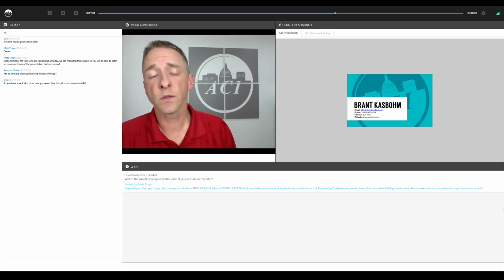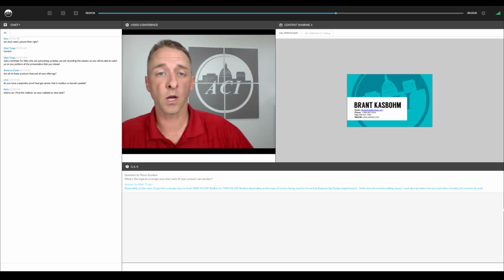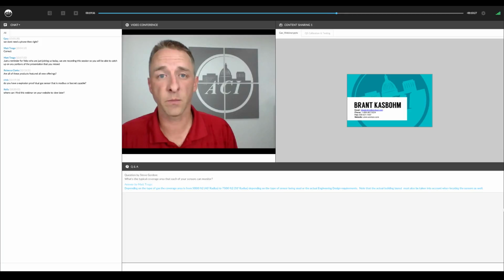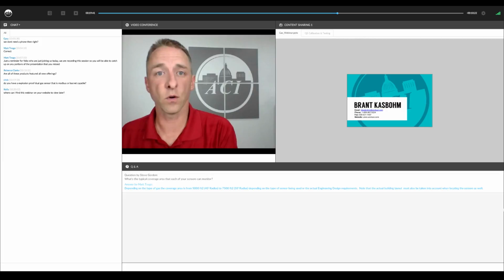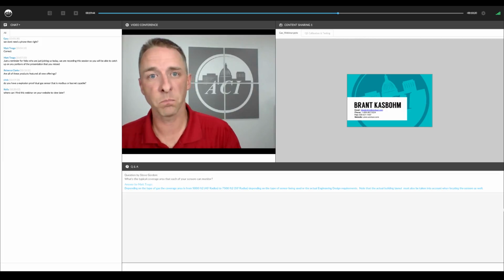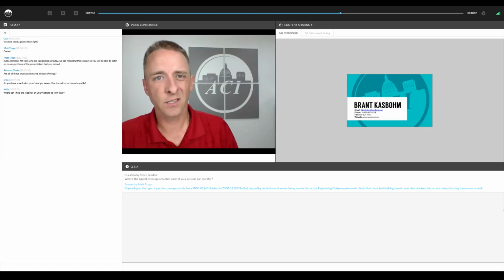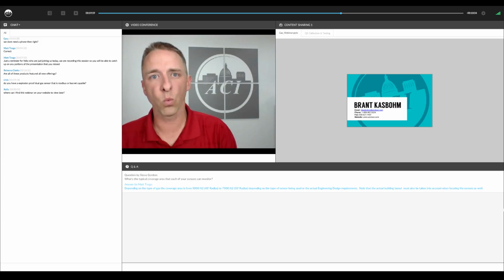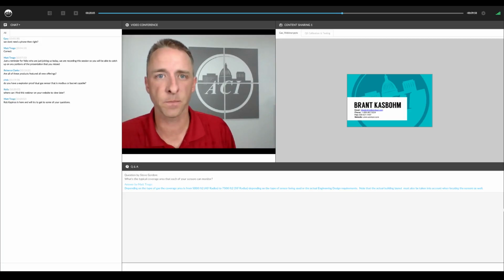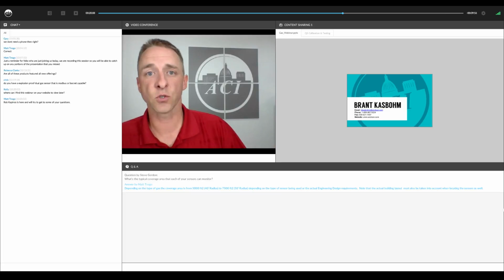The CO2 sensors don't wear out over time, and if you're using the ABC Logic software, there's no need for future or periodic recalibration or maintenance for those sensors. For the toxic and combustible sensors, most of them are electrochemical in nature, and they do wear out over time. So the typical life expectancy is anywhere from 4 to 6 years. We've seen them go well beyond that because it is based on the actual levels of gas in the space. So if the sensors are in an area where there's high levels of CO, for example, that sensor will wear out faster.